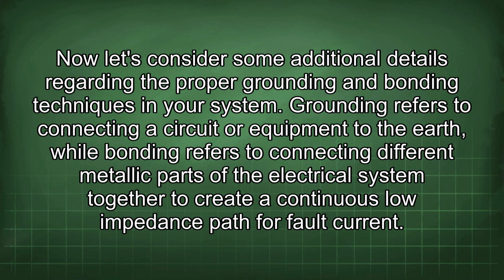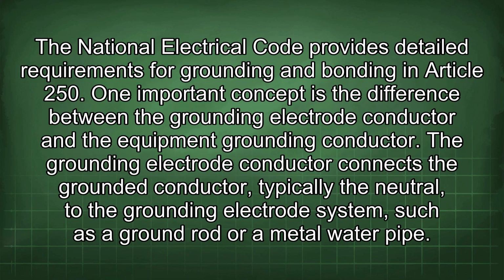Now let's consider some additional details regarding the proper grounding and bonding techniques in your system. Grounding refers to connecting a circuit or equipment to the earth, while bonding refers to connecting different metallic parts of the electrical system together to create a continuous low impedance path for fault current. The National Electrical Code provides detailed requirements for grounding and bonding in Article 250. One important concept is the difference between the grounding electrode conductor and the equipment grounding conductor. The grounding electrode conductor connects the grounded conductor, typically the neutral, to the grounding electrode system, such as a ground rod or a metal water pipe.